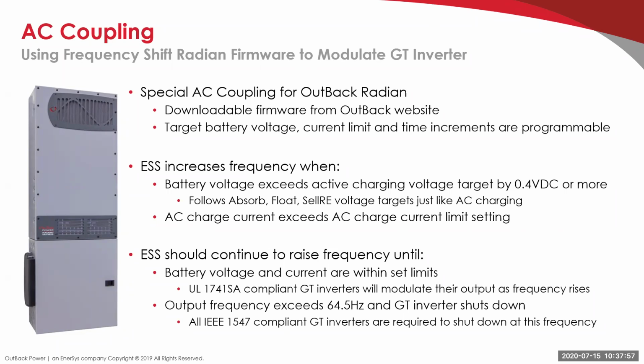One thing that is, I believe, unique about the Outback system versus at least some of our competitors is that if the AC charge current exceeds the AC charge current limit setting, we will also increase the frequency shift. Now, we will continue to increase frequency past the 60.5.